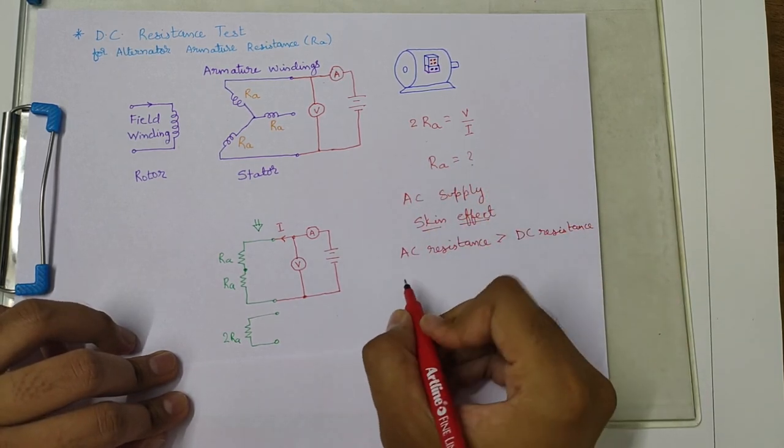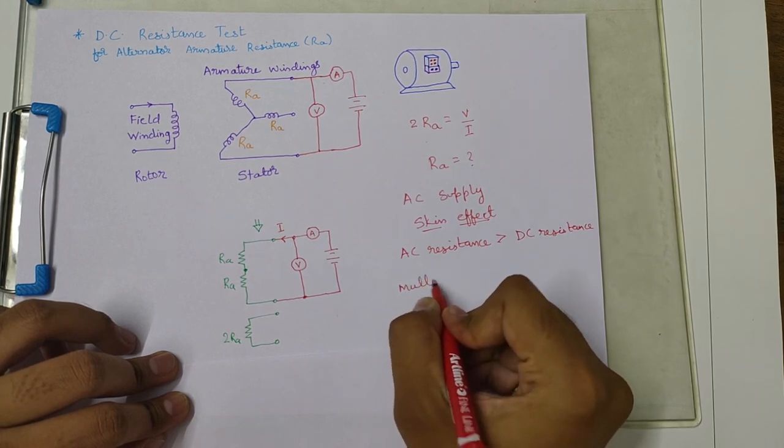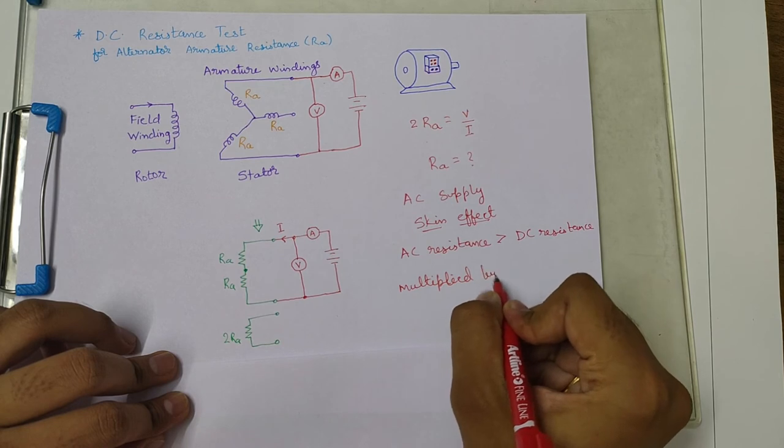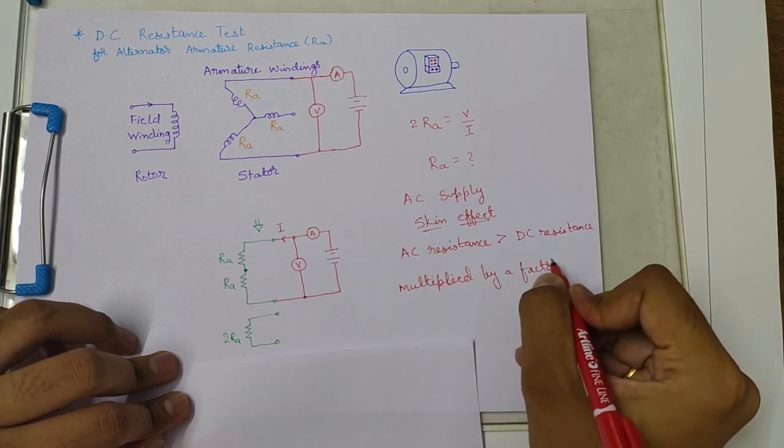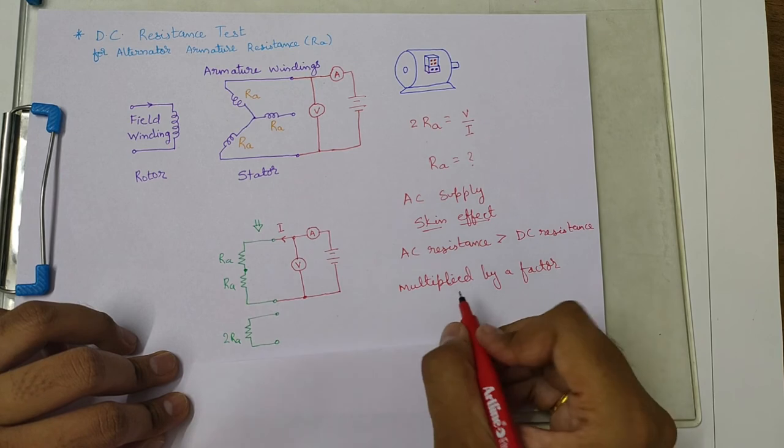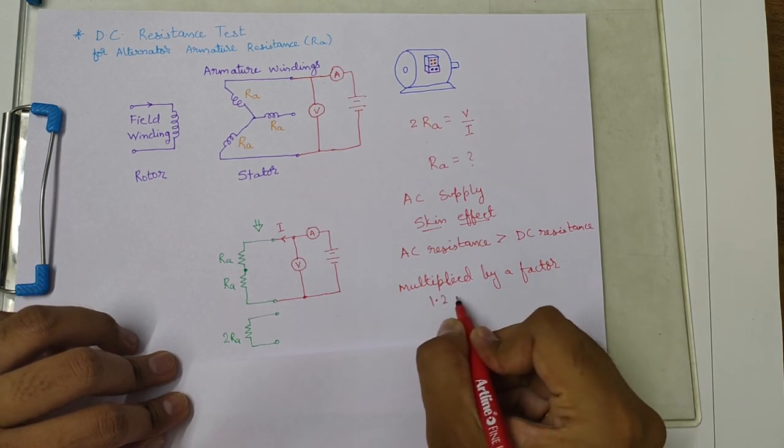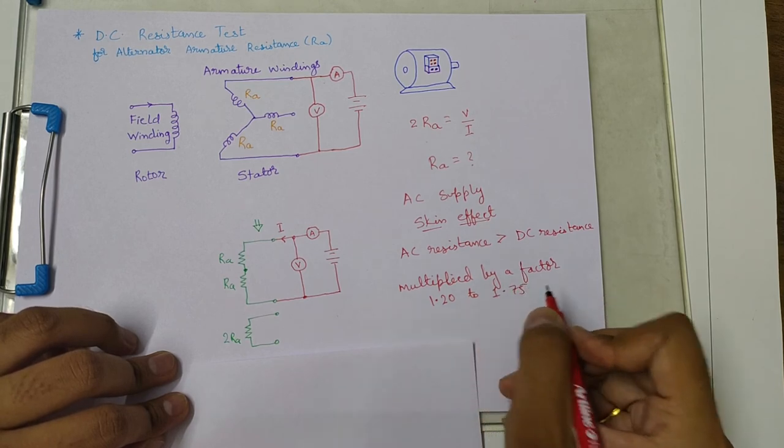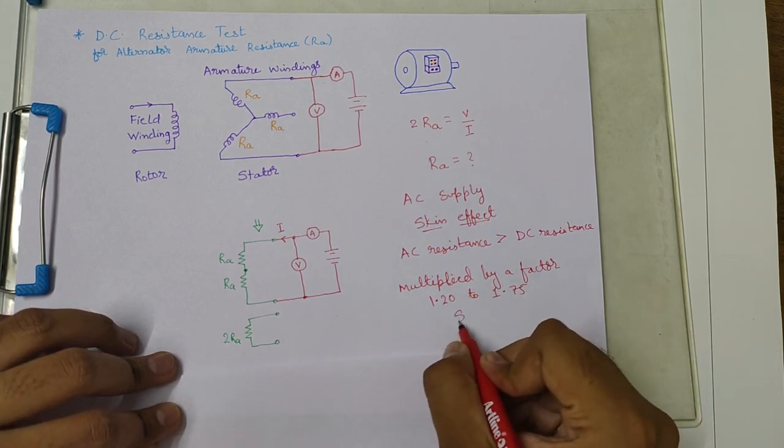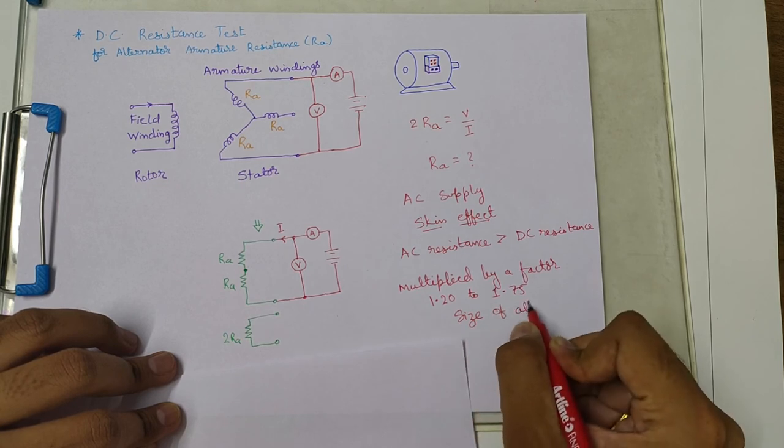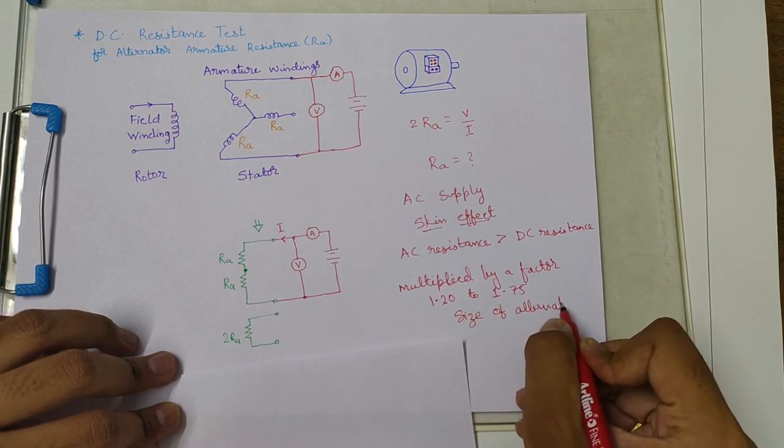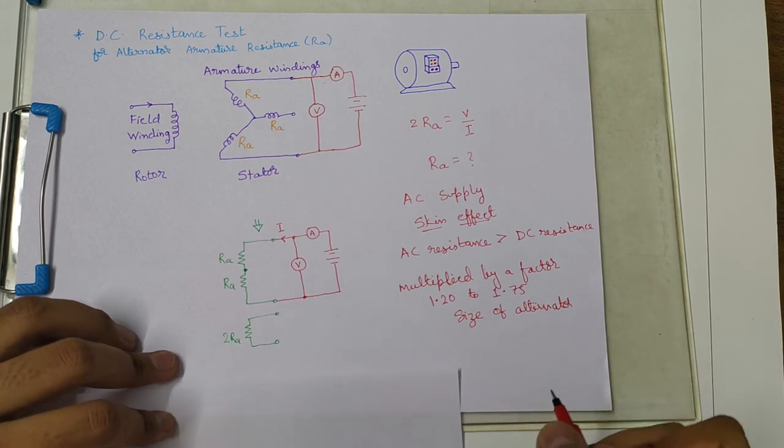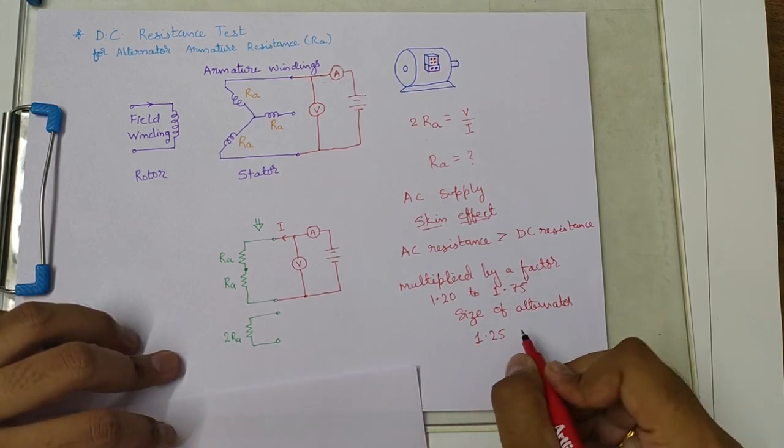So what do we do with this value? Usually it is multiplied by a factor of 1.20 to 1.75 depending on the size of the alternator or the rating of the alternator. Usually a 1.25 multiplier is taken.